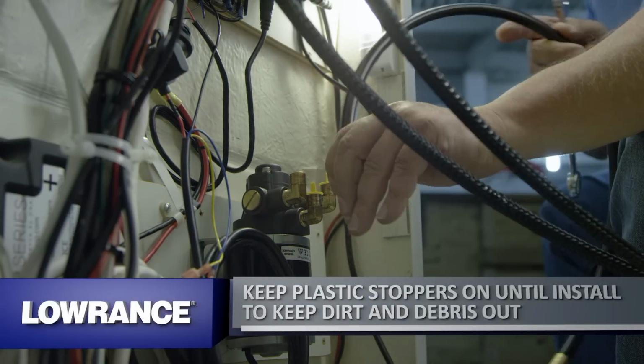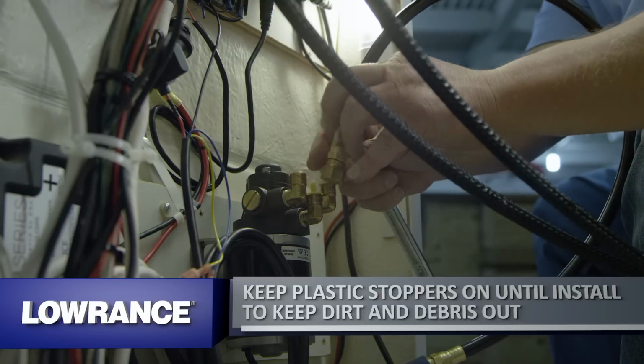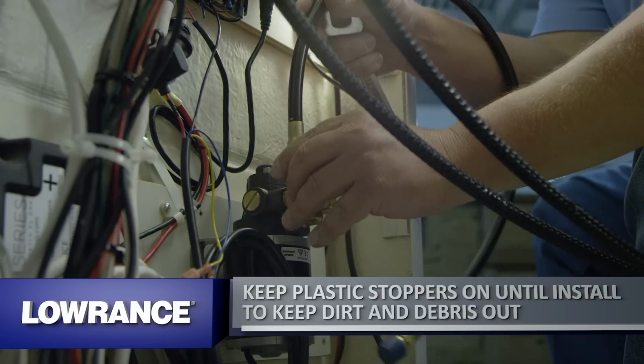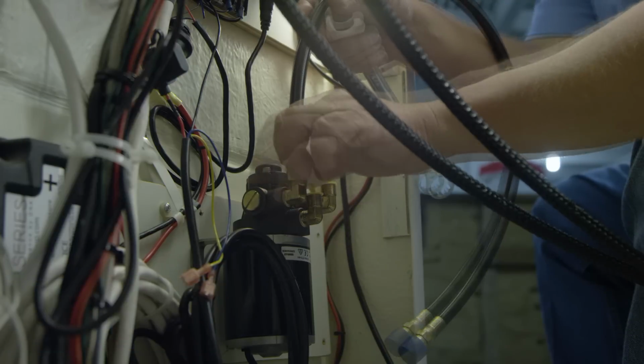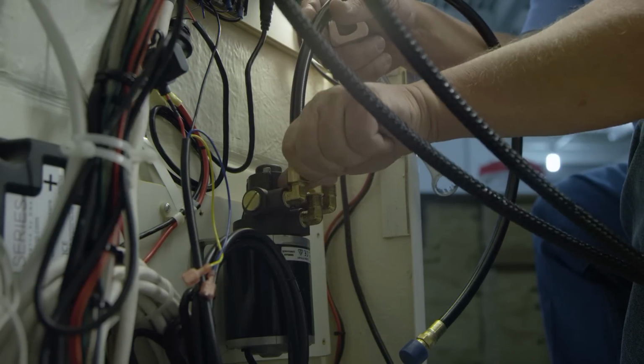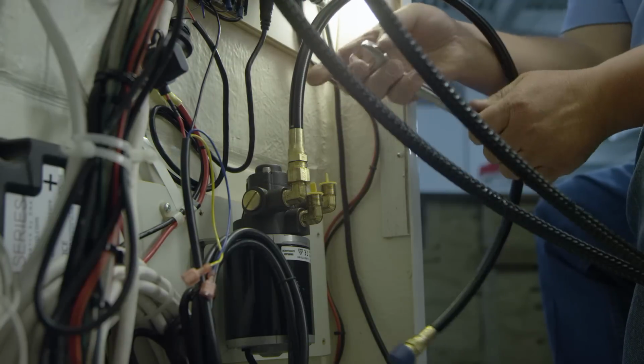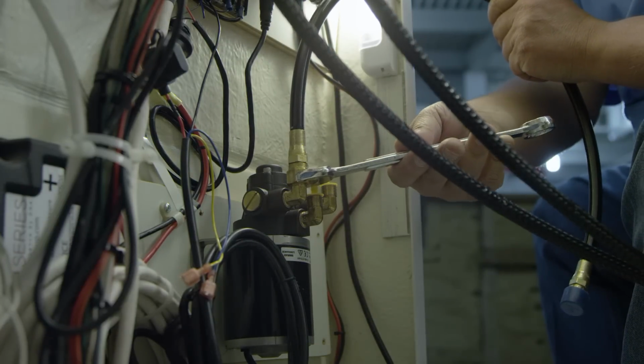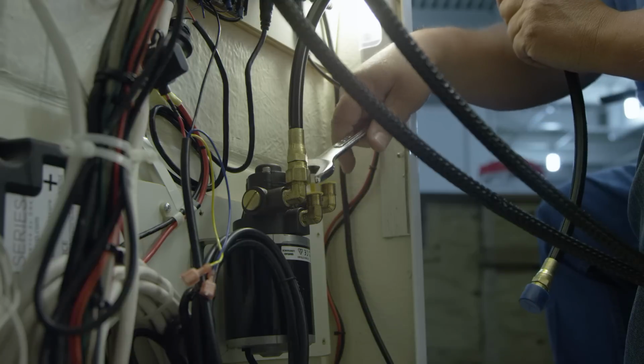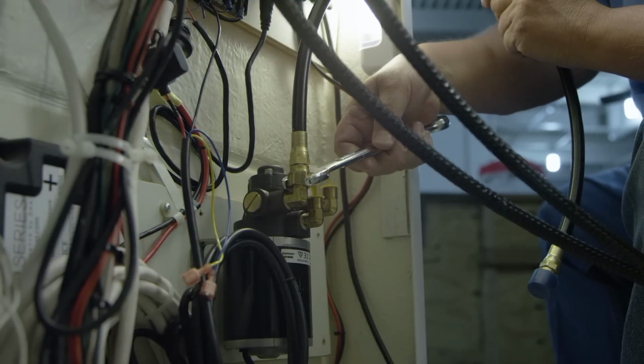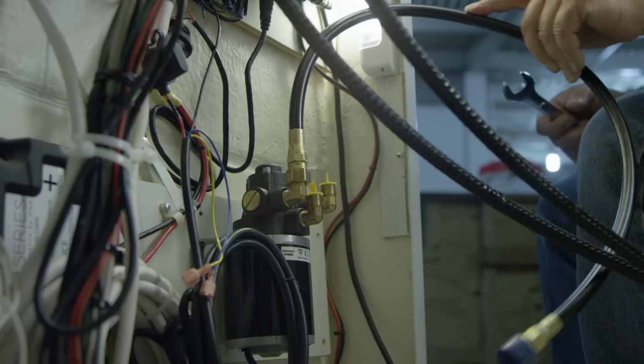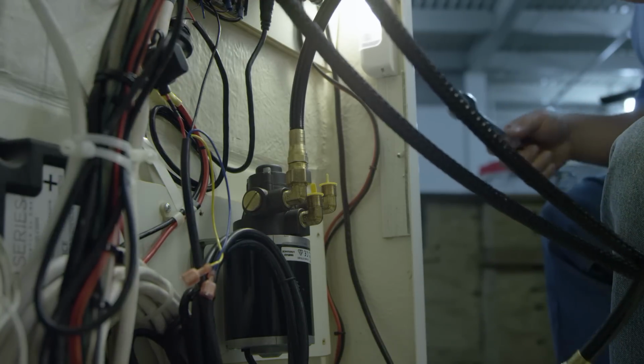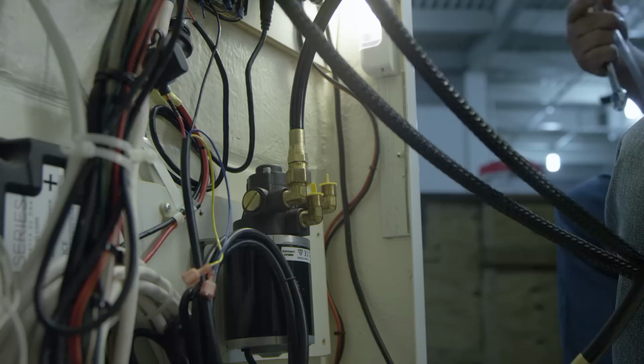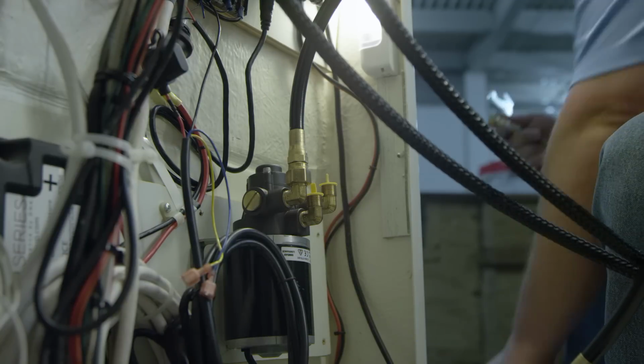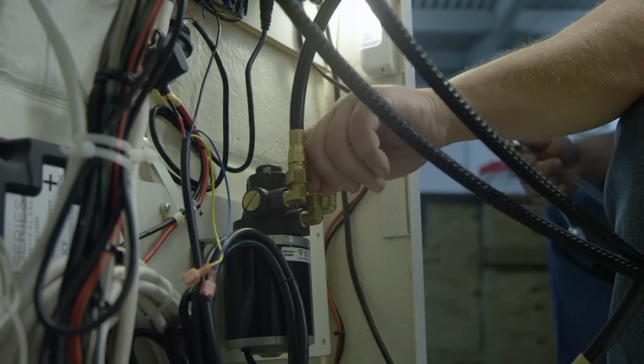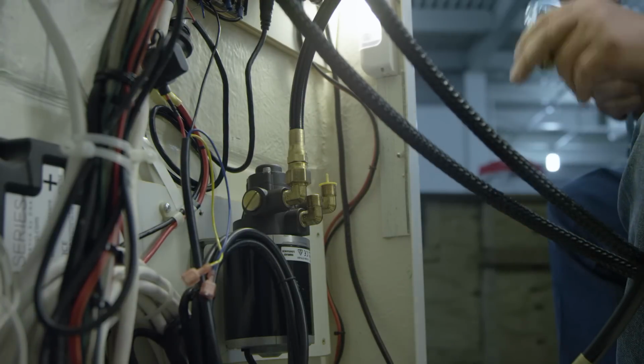We've got 3 hoses to connect here. You're going to have 2 dark hoses that go on your outside fittings, and 1 clear hose which goes in the middle fitting. That clear hose is your return line hose. It's going to allow you to see the air bubbles and everything that go to your helm that we bleed out of the system once we start bleeding it.